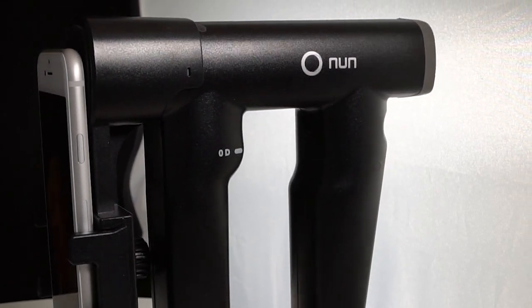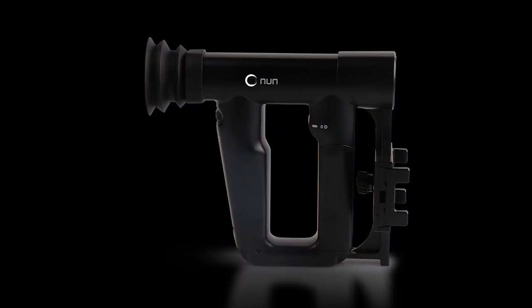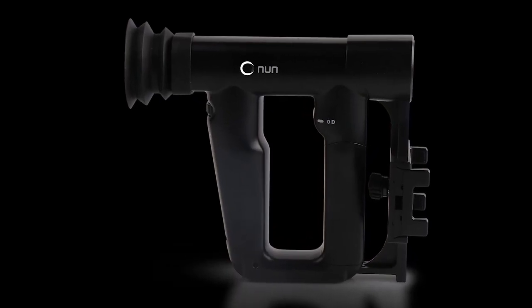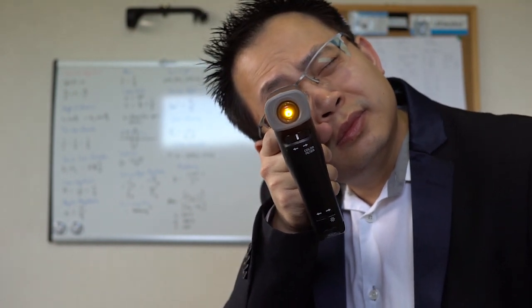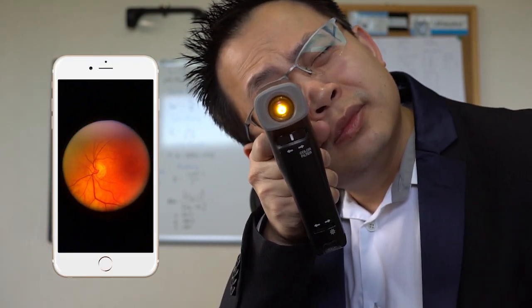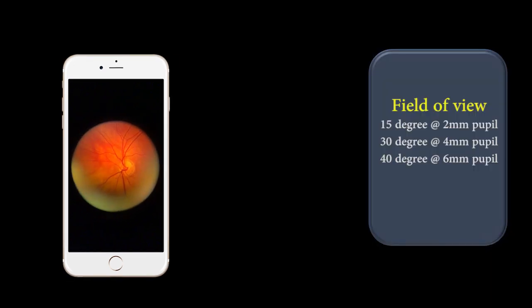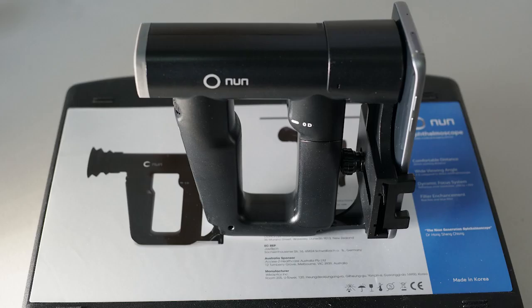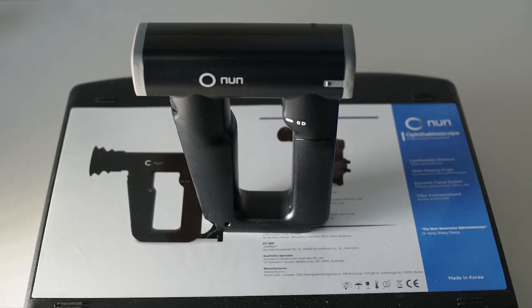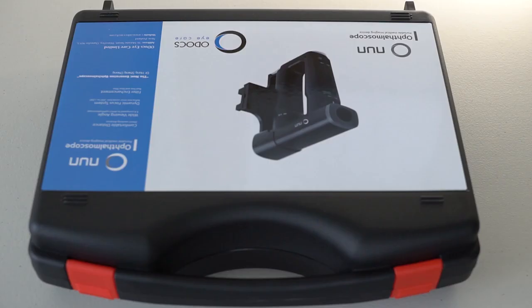Odocs Nun, the next generation ophthalmoscope. Designed for the 21st century, Odocs Nun is the only handheld wide-field ophthalmoscope that is compatible with any smartphone. The Odocs Nun offers 8 times wider field of view compared to the direct ophthalmoscope. In other words, you can see more of the patient's retina. The device can be used with or without a smartphone, and more importantly, it is independent of the type of smartphone used.